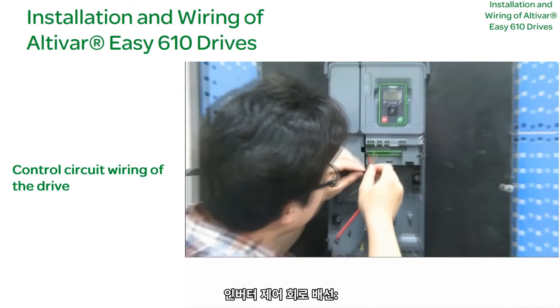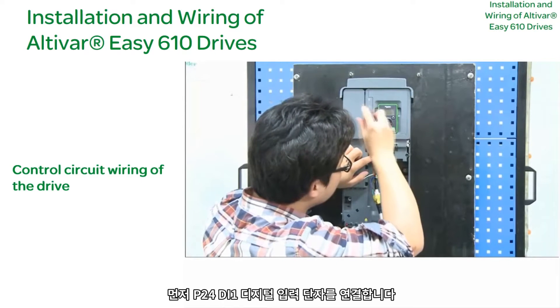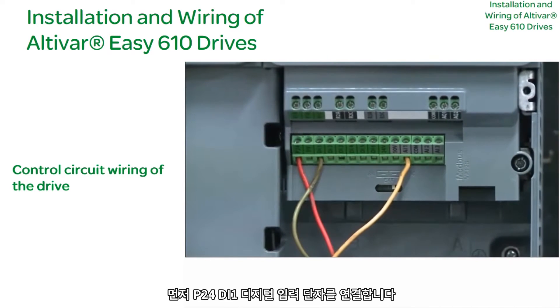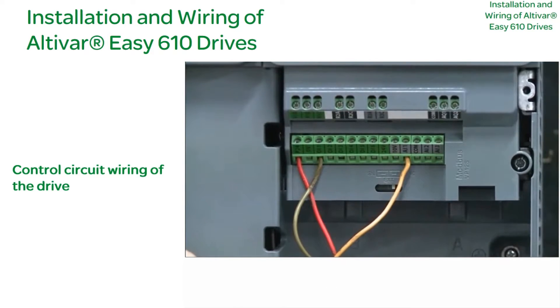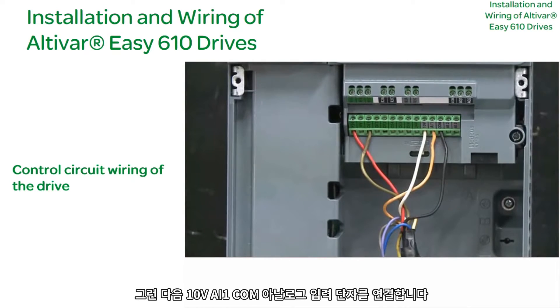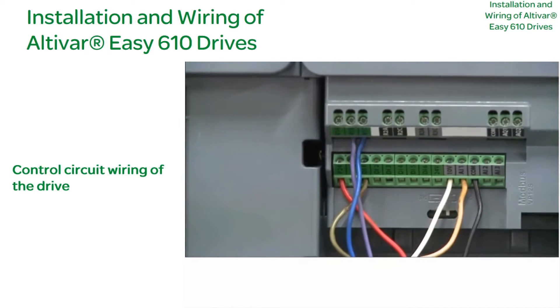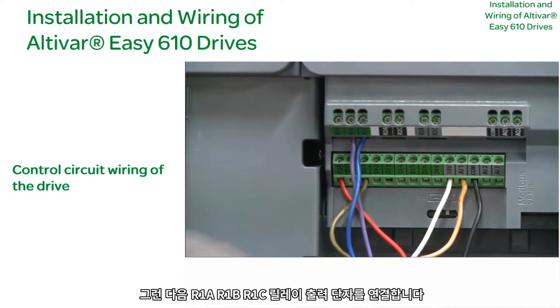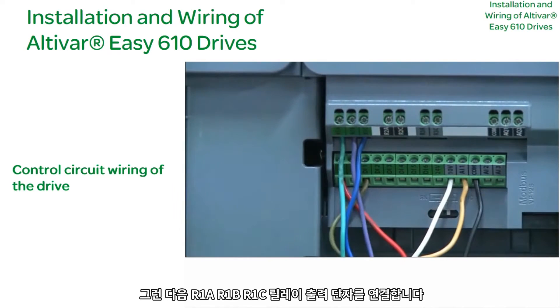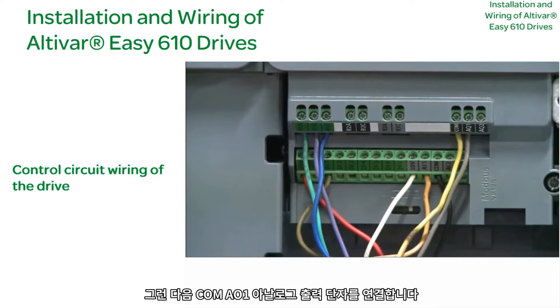Drive Control Circuit Wiring: First, connect the P24/DI1 digital input terminal. Then connect the 10V-AI1-COM analog input terminal. Then connect the R1-A, R1-B, R1-C relay output terminal. Then connect the COM-AO1 analog output terminal.